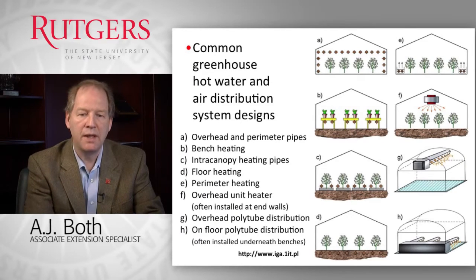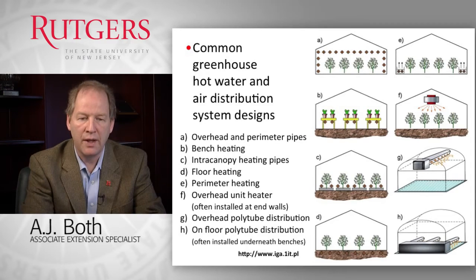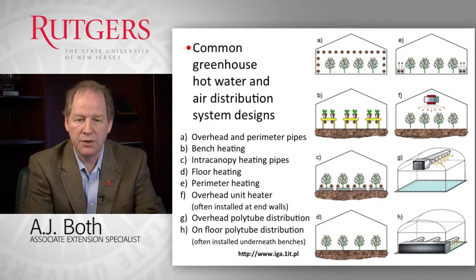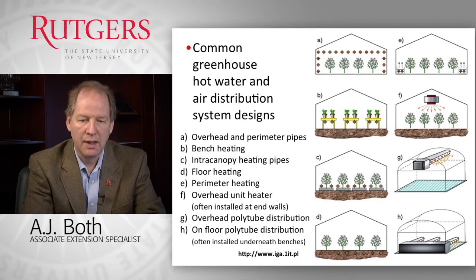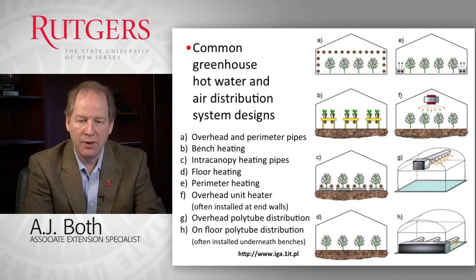In this slide you see several common installation systems for both hot water and hot air heating systems in greenhouses. We can have pipes along the overhead and perimeter of the greenhouse, pipes underneath benches, or pipes in between rows of plants that can also be used for transportation purposes, for example in tomato or pepper crops. We can have floor heating systems where we put heating pipes inside the floor — either a dirt floor or a concrete floor. We can also have only perimeter heating, typically with additional fan capacity to distribute that heat uniformly.